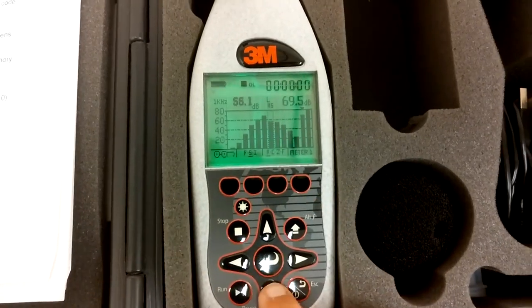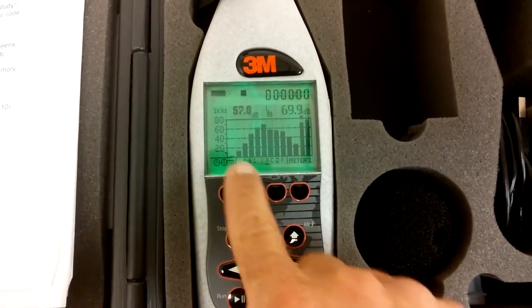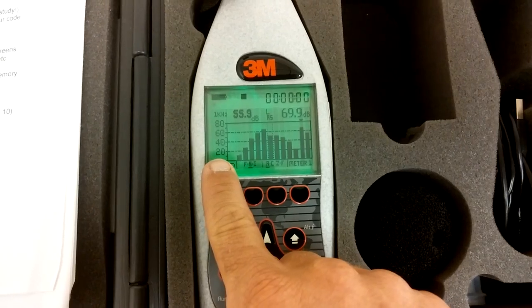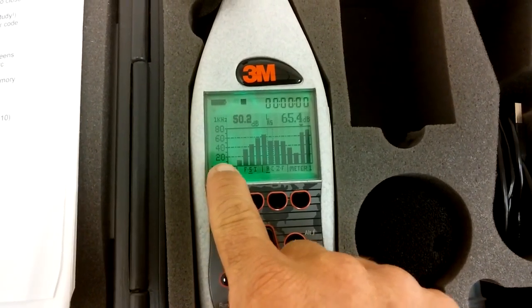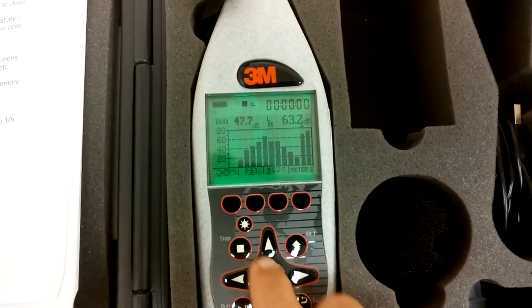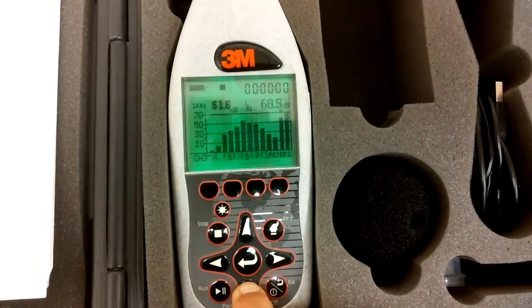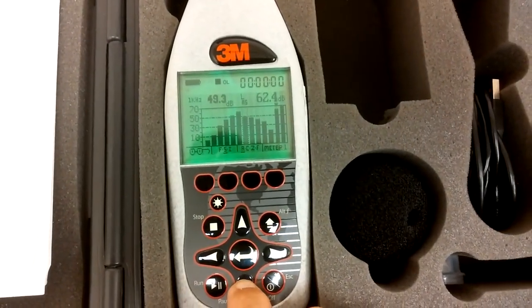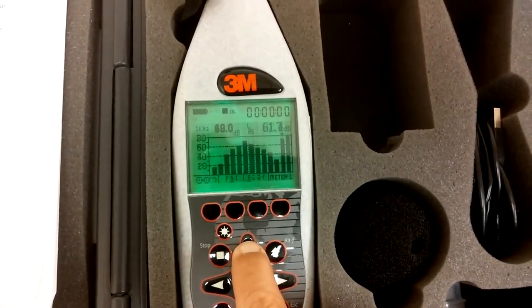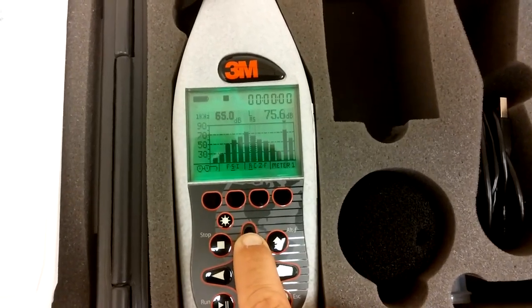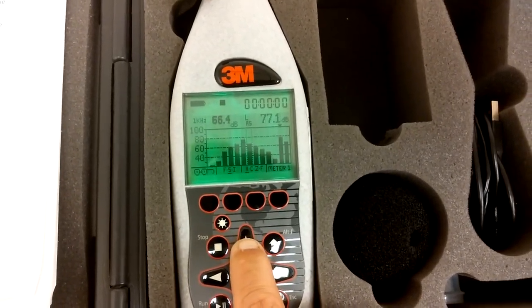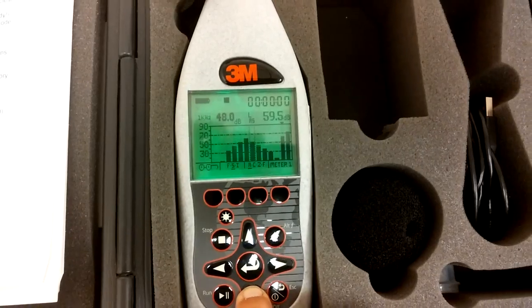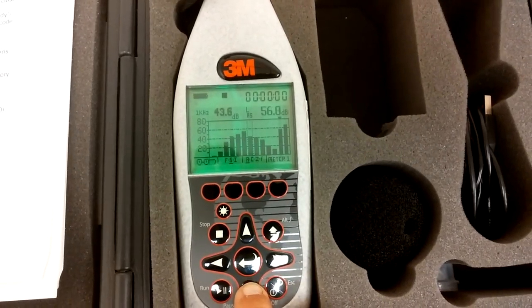All right, using the up and down buttons, we want to make sure this range is from 20 to 80 decibels. We're already there, 20 to 80, but if we went down, you can see it'd go from 10 to 70, or if we went up, it'd go from 30 to 90 and even higher, 40 to 100. We want it at 20 and 80.